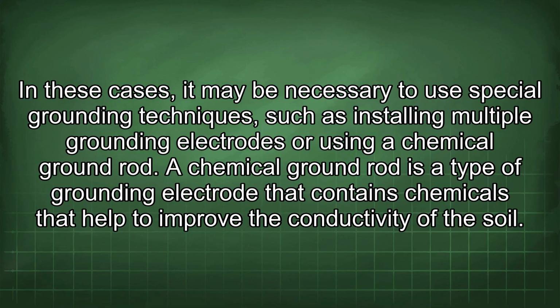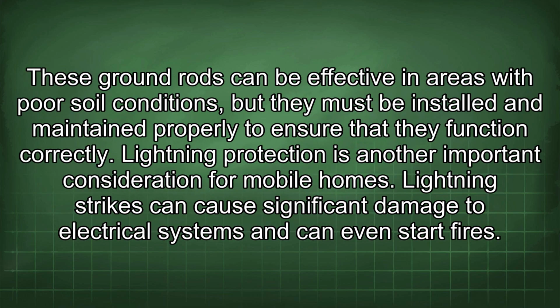A chemical ground rod is a type of grounding electrode that contains chemicals that help to improve the conductivity of the soil. These ground rods can be effective in areas with poor soil conditions, but they must be installed and maintained properly to ensure that they function correctly.